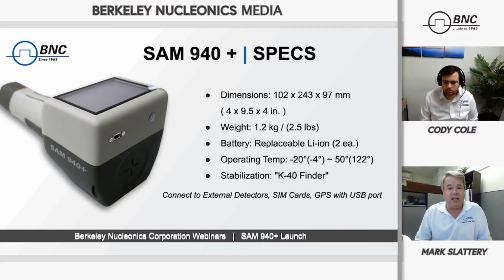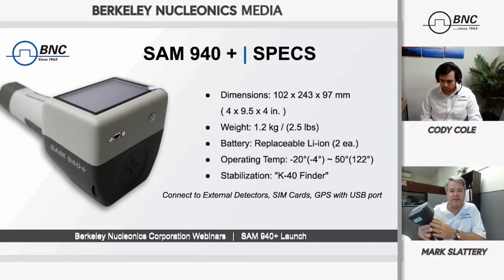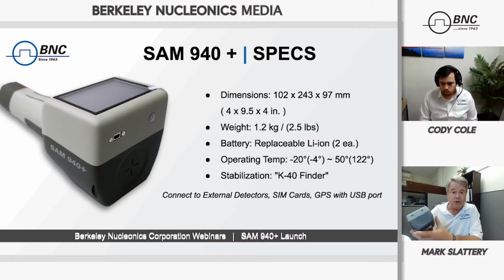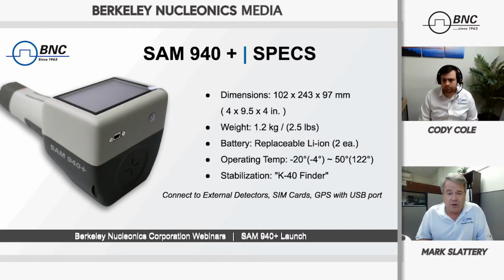Stabilization is also used in the calibration. If you're not familiar with it, why is stabilization important? If you're operating in that temperature range, say -4 up to 122 degrees Fahrenheit, the temperature can eventually start to affect the analog device, which is the main device in here - the tube, the photo multiplier, is an analog device greatly affected by time and temperature. So your energy calibrations may start to drift a little one way or the other. By virtue of this stabilization running in the background and constantly using K40 as its reference, we can make sure that as temperatures change, the SAM keeps up with that change, automatically adjusting and keeping the device in calibration.